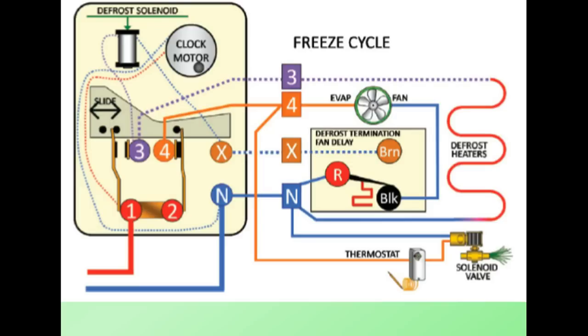It's really important to understand how this works and why. Know that how this is wired in these diagrams is not always what you're going to see. Sometimes the defrost clock is wired up through the attic or through a crawl space to the evaporator itself, so it's not going to be in close proximity. You need to understand the relationship between the two.